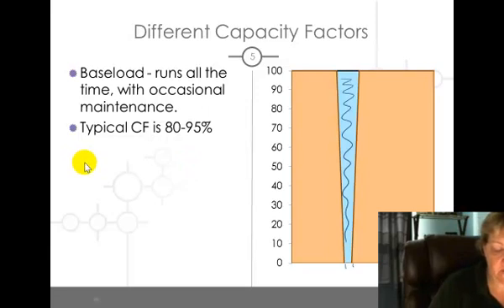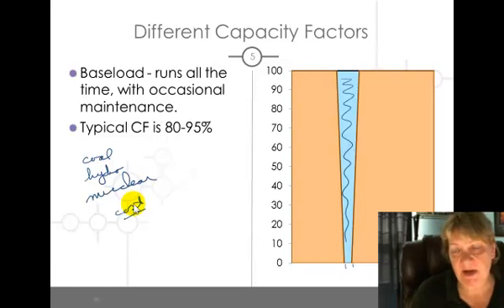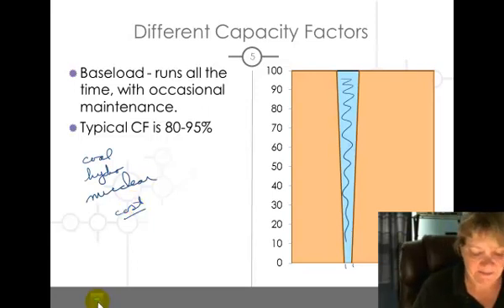Typical capacity factors are somewhere between 80 and 95 percent for units that are baseload. Baseload units are frequently coal. Hydro is usually baseload. Nuclear is usually baseload. Why are these picked over others? Cost. Usually they're a little less expensive. They're probably usually the cheapest money on the grid. There are some distortions in the market right now that's changing that answer a little bit, but that's still kind of where it sits.